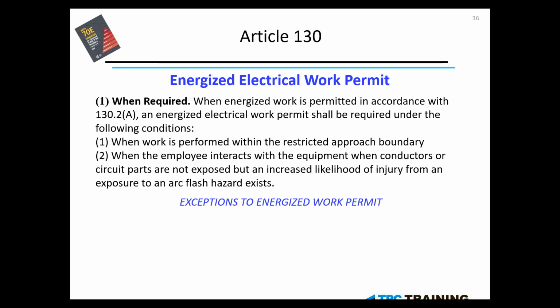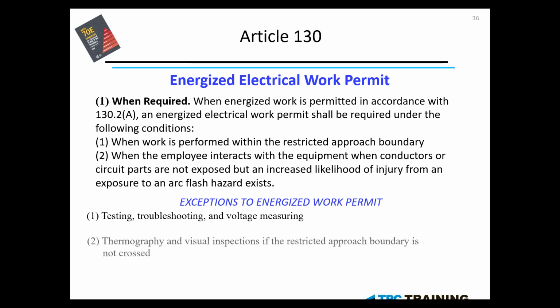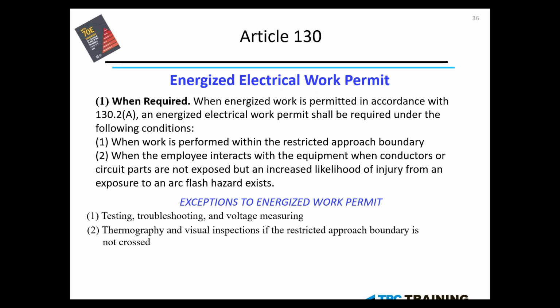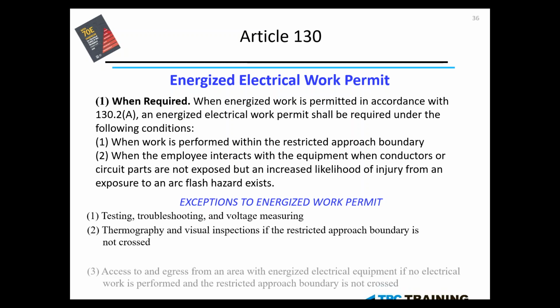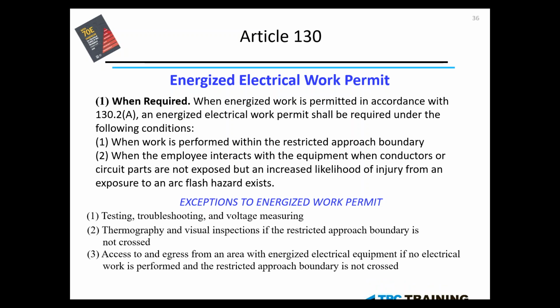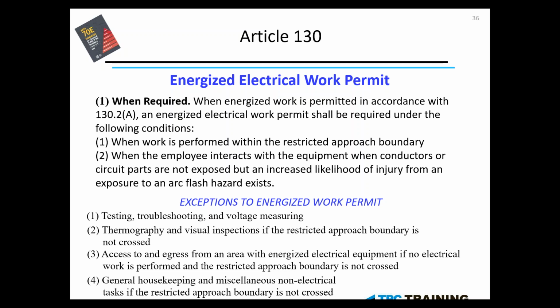The 4 exceptions to an energized work permit: while testing, troubleshooting, or voltage measuring, during thermography or visual inspections if the restricted approach boundary is not crossed. Access to and egress from an area with energized electrical equipment if no electrical work is being performed and the restricted approach boundary is not crossed. And general housekeeping and miscellaneous non-electrical tasks if the restricted approach boundary is not crossed. So these are 4 exceptions when it is not necessary to pull an energized work permit. However, these individuals still need to be protected against the hazards. It's just the permit they're talking about here in 130.2.